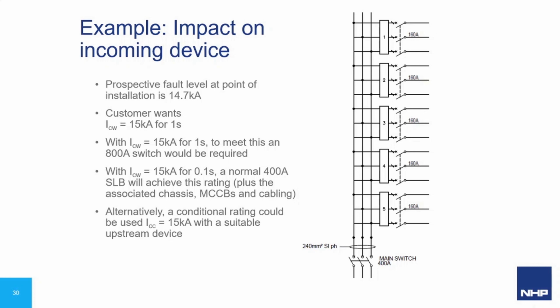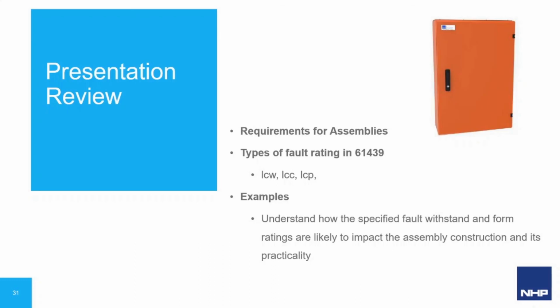Alternatively, we could consider using a conditional rating, an ICC of 15 kA with no associated time. Again, this requires us to nominate a specific upstream device that will lend protection to the 400 amp main switch and other equipment within our assembly. So looking back on what we have discussed, we have learnt about the requirements of our switchgear assemblies. We have looked at the different withstand ratings available for switchgear assemblies and how they are derived. And we have also looked at some practical examples and how the different ratings can impact the final assembly.